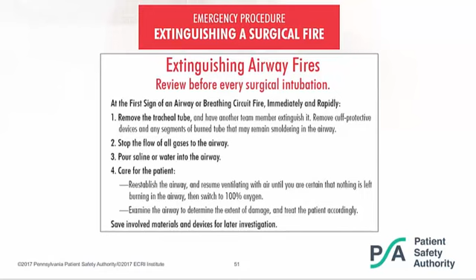If a tracheal tube catches fire, the first thing to consider doing is to remove the tube from the patient. If that can be done with item 2, which is stopping the flow of all gases to the airway, then that's fine. But it's essential to get that tube out of the patient and then to pour saline down into the airway and care for the patient. And here's why. When a tracheal tube catches fire, this is a PVC standard tube, it is literally a blowtorch burning down in the lung.